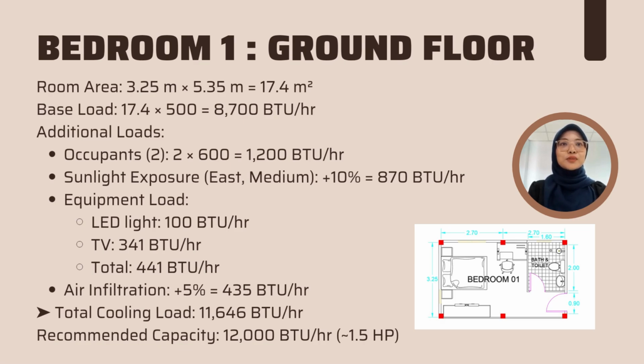For bedroom 1 located on the ground floor, the room size is 3.25 by 5.35 meters, giving us an area of 17.4 square meters. Using the standard of 500 BTU per square meter, the base load is 8700 BTU per hour. Next, we add the heat gain from 2 occupants, which add 1200 BTU. Since the room faces east and has medium sunlight exposure, an additional 870 BTU is considered. For equipment, we included a TV and LED light, adding up to 441 BTU.